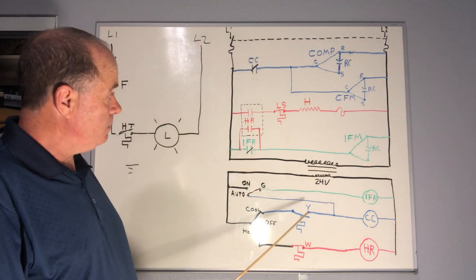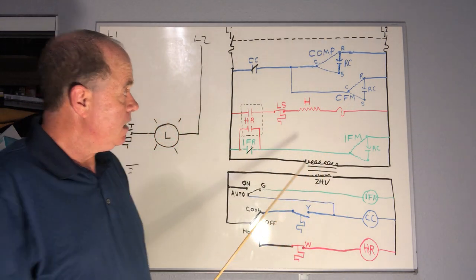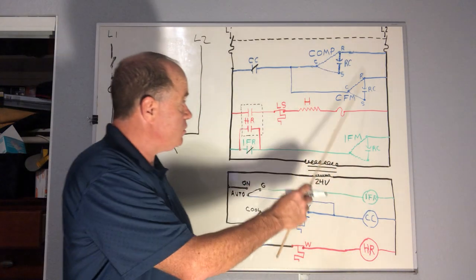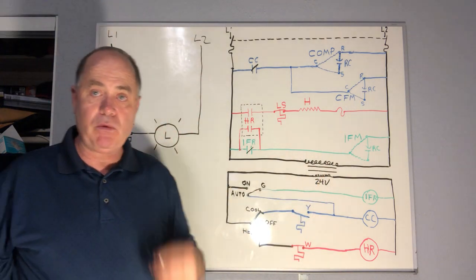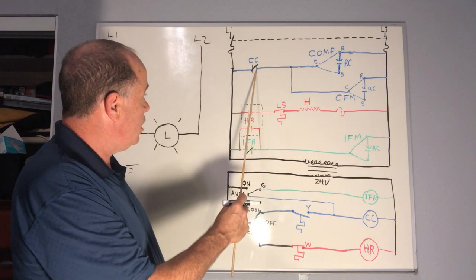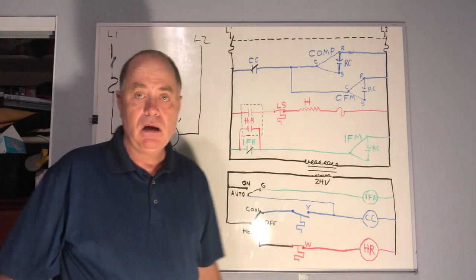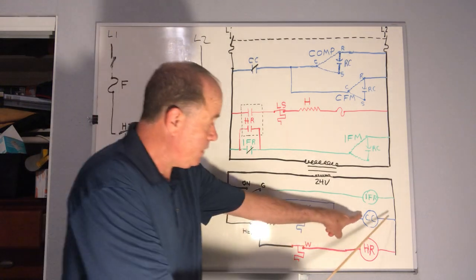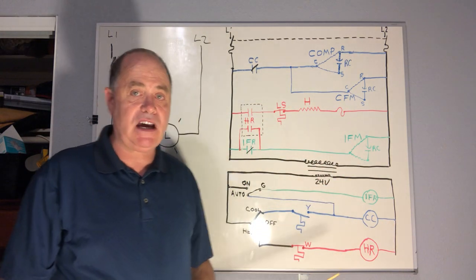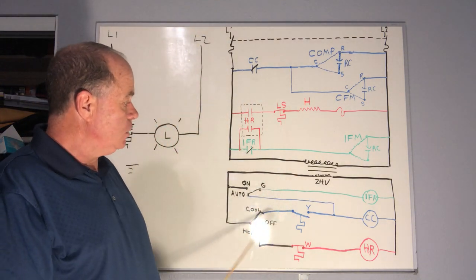If neither the compressor nor the condenser fan runs but the indoor fan runs, suspect what the compressor and condenser fan motor have in common — that would be the contactor. Either the coil might be burned open, or the contacts are frozen open. If you're getting 24 volts to the coil but it's not closing to give the motors their voltage, replace the contactor. Process of elimination.